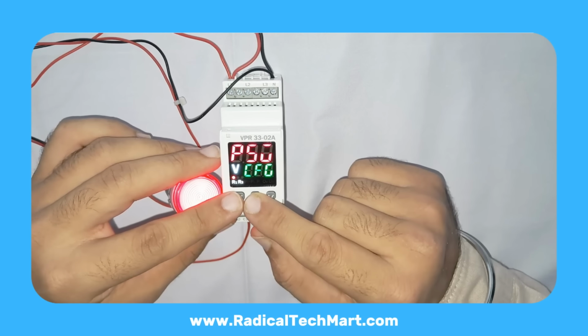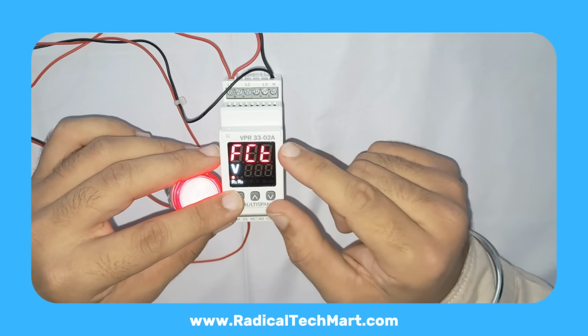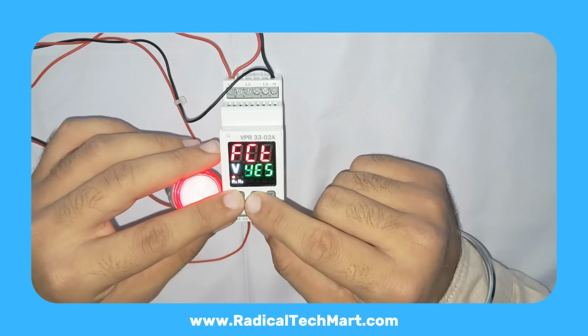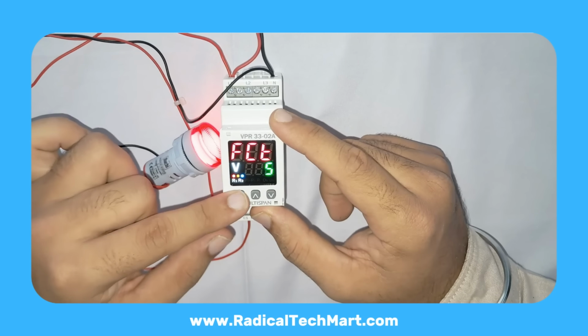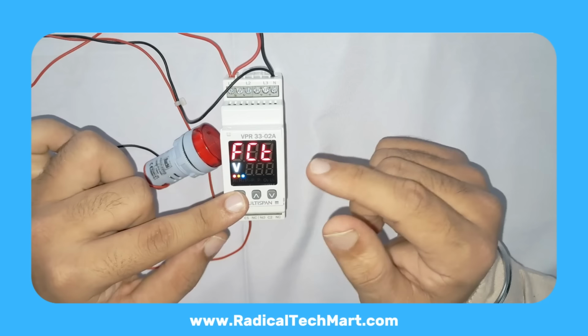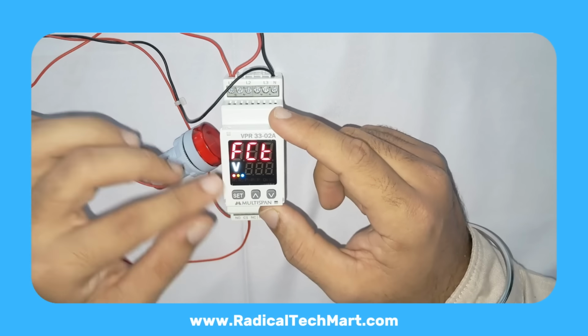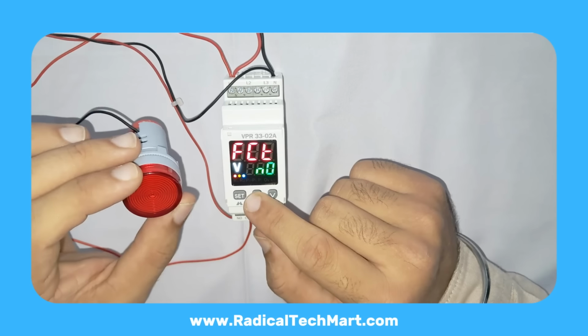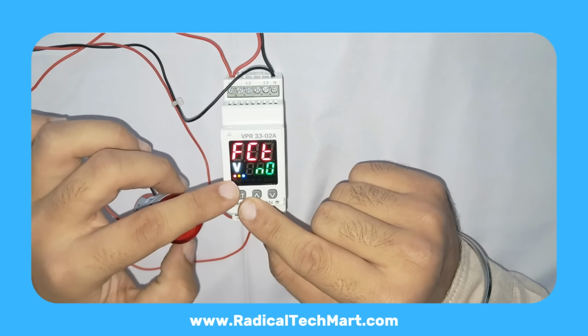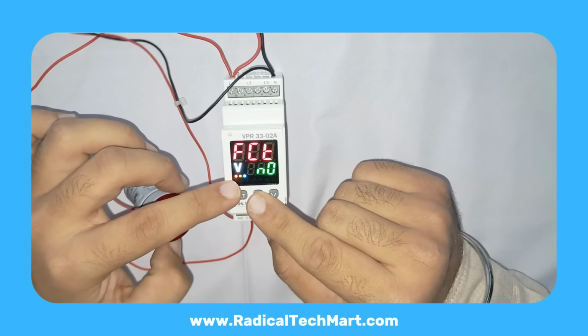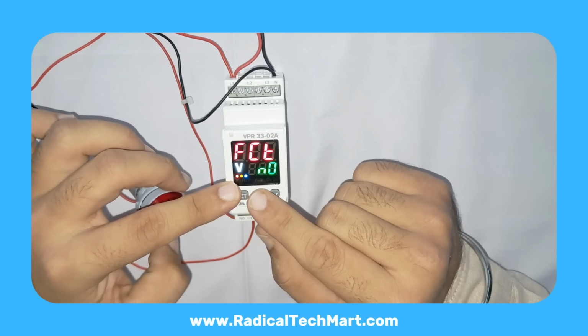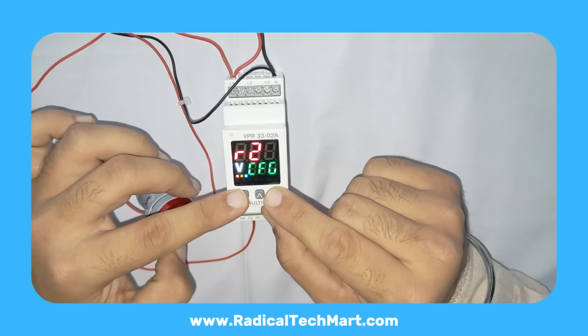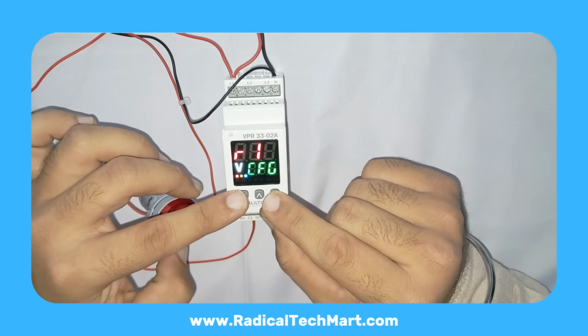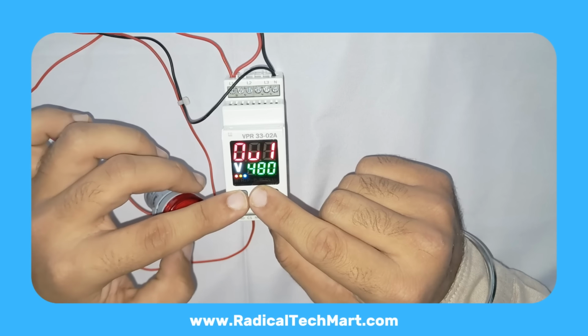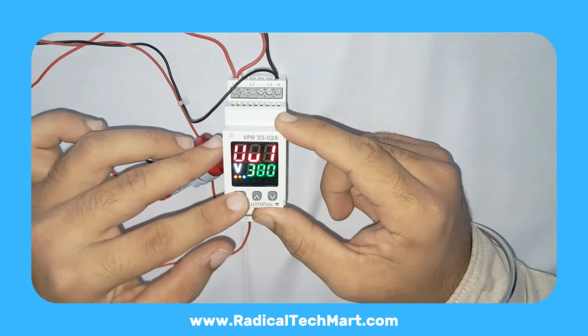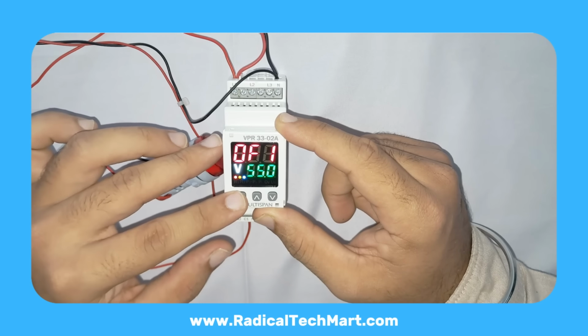Press up again. You will see factory reset. If you want to restore default values, press Set. Select Yes. Then press Set again. All the parameters will go back to the factory settings. After factory reset, the device will typically default to 3-phase, 4-wire mode, and all basic voltage, frequency, and delay settings will return to default. When the relay is in 3-phase, 4-wire mode, 2 extra protections become available.